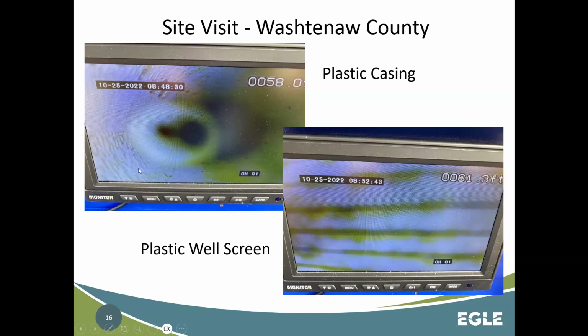But when you take a look at the casing here, you can kind of see some of this calcification on the side, kind of build up. You can also see on the screen, there's some iron or iron bacteria, great places to harbor bacteria and for bacteriological growth. Our recommendation to the campground was, with the water quality issues that they've got here and the general lack of use, they might have to actually develop this every year and disinfect it to keep it free. So that pretty much wrapped that one up as well.